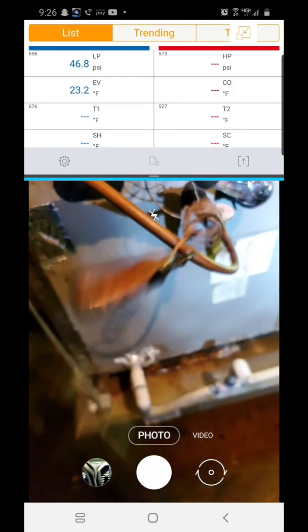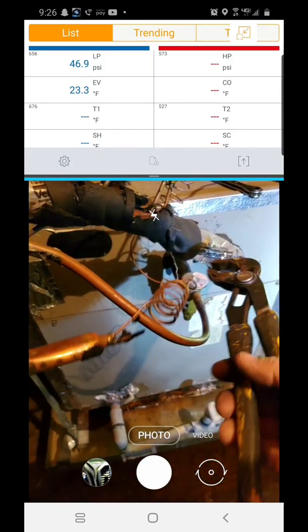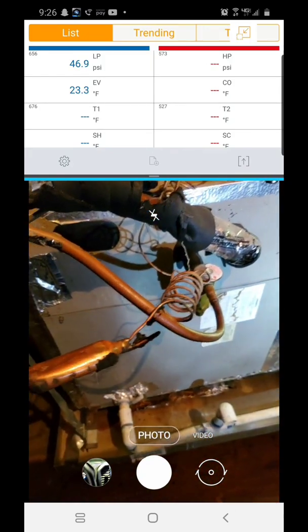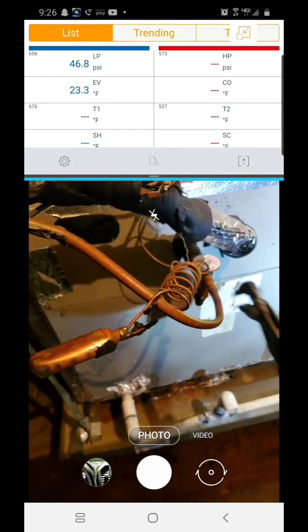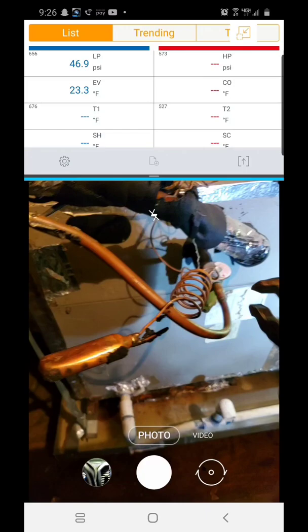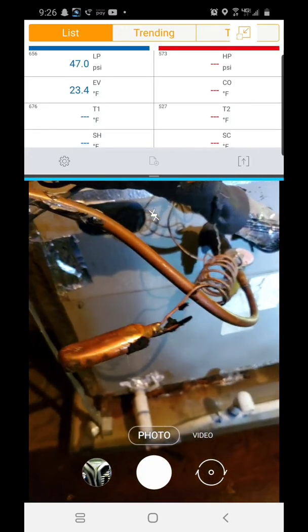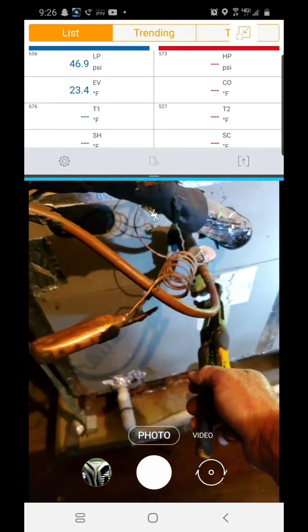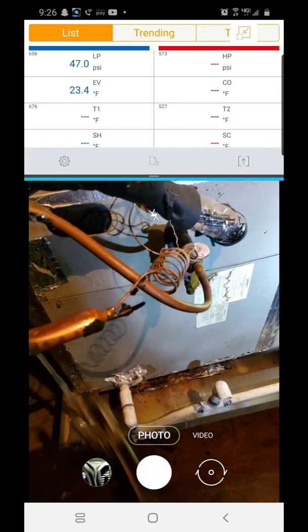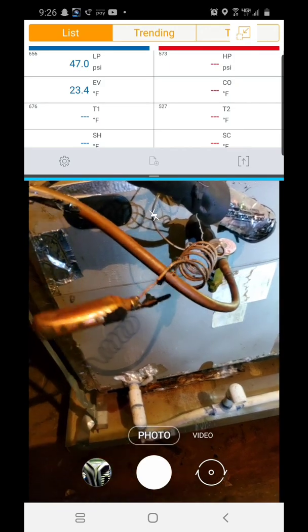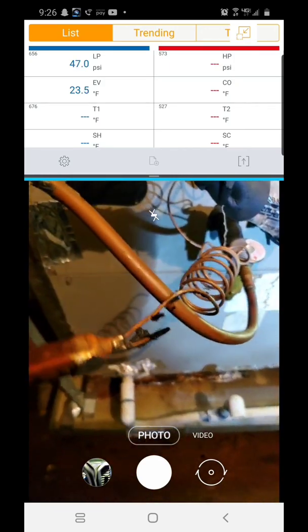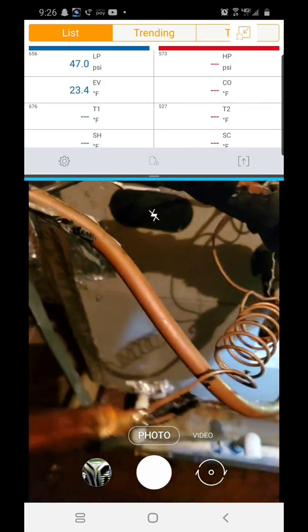So if it doesn't get it, I'm gonna come up here like freaking brazing a Schrader on this thing, pressurize that dome. But if it's a restriction it ain't gonna help. But it's made a difference - I pulled this off, it made a difference, and I turned this valve and then pulled this off. See there, it's up to 47. Oh man, if I could just get a little bit more I could probably get through the night.